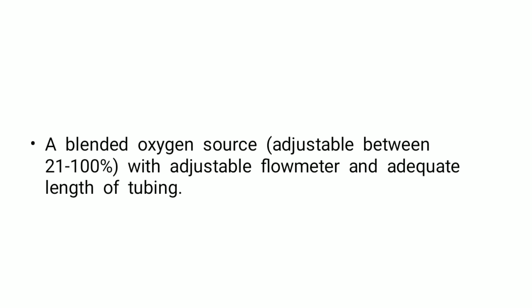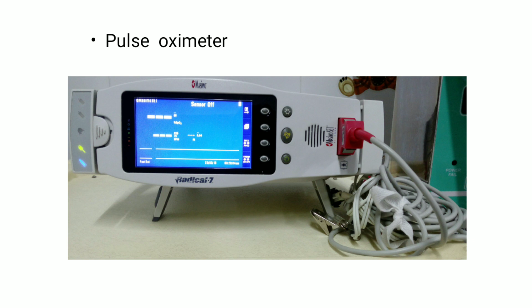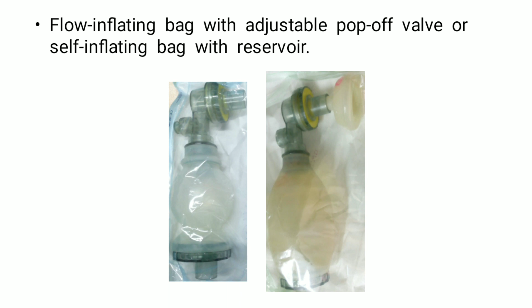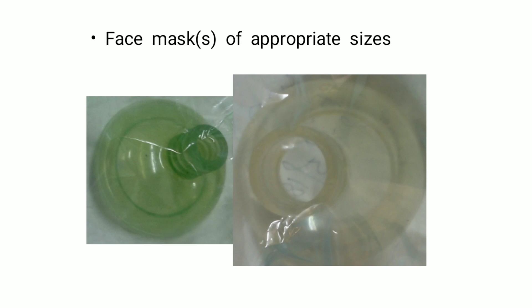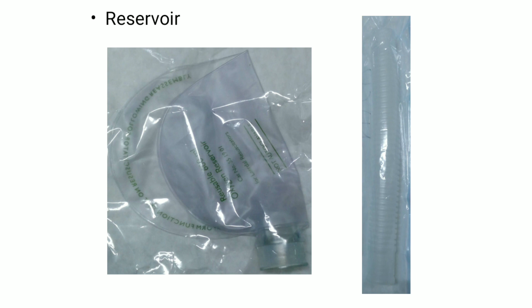A blended oxygen source is required, which should be adjustable between 21 to 100% FiO2 with an adjustable flow meter and adequate length of tubing. This is the pulse oximeter. Then a flow-inflating bag with adjustable pop-off valve or a self-inflating bag with reservoir. These are the self-inflating bags. One is for preterm, the other one is for term. The first one is of 250 ml, the second one is of 500 ml. And these are the face masks of appropriate sizes. These are the reservoirs. They are of two types. The first one is the bag reservoir and the second one is the tube reservoir. Reservoirs help in increasing the concentration of the oxygen.